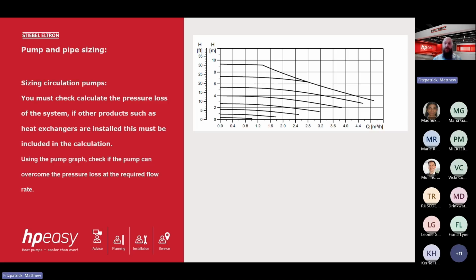At that stage, when you have the full pressure loss of the system, you can compare it to what's called a pump graph, which we have on the screen here. You can then refer to the manufacturer to see what their minimum flow rate or nominal flow rate is, normally in meters cubed per hour, and you can see if your pump can overcome the system pressure at the required flow rate the manufacturer specifies.